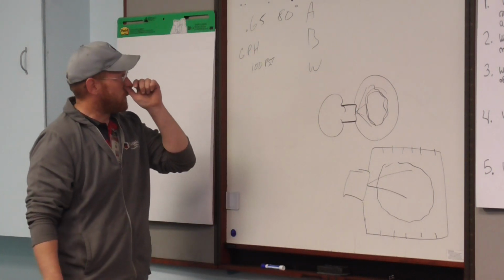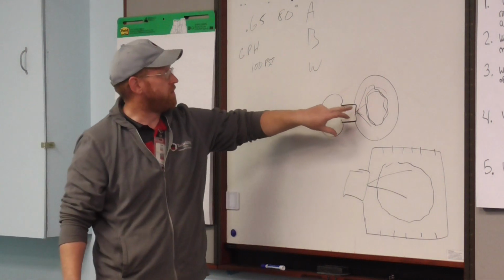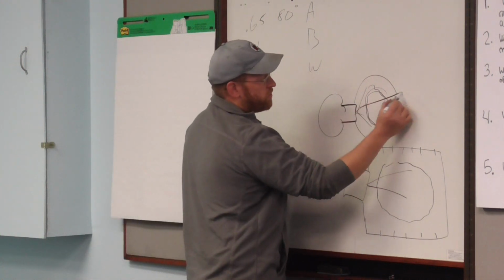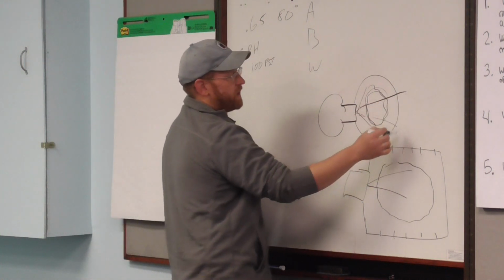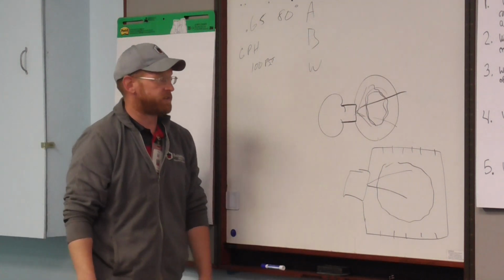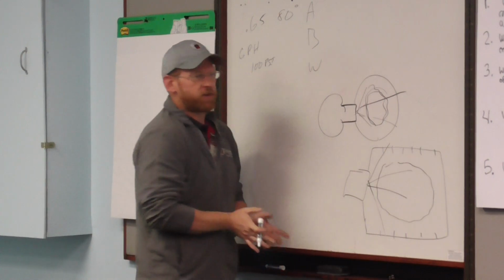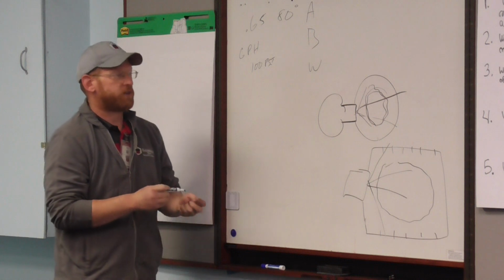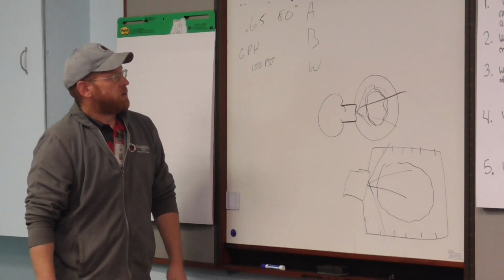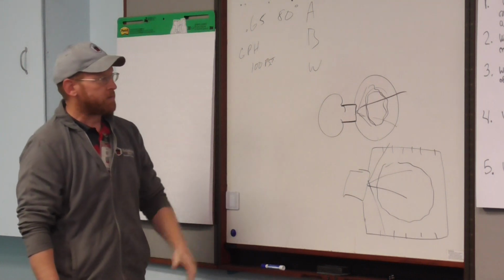If you change this angle too much, if you put a narrow angle on something like this, it's gonna spray out and your oil's gonna hit the back of it, and it's gonna coat the back of that thing with oil, burn it up, do a lot of nasty stuff to it. Same thing with here. It sprays out, it'll get all over the sides and kill your combustion, and nothing will get to the back. Usually burn a hole there. Leave hot spots.